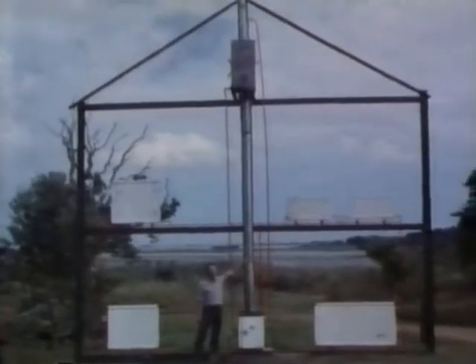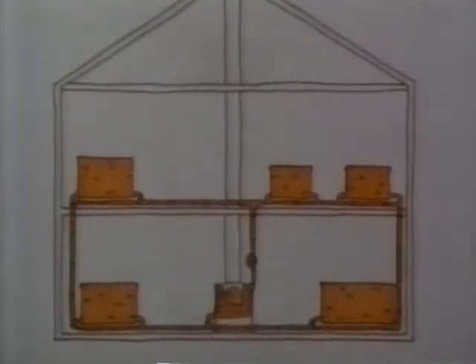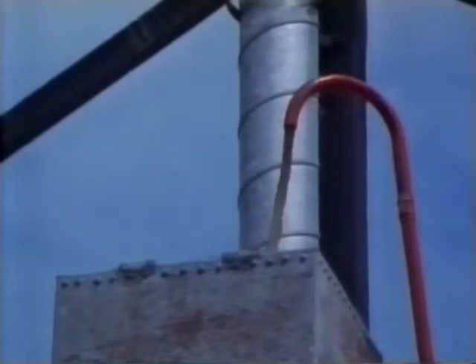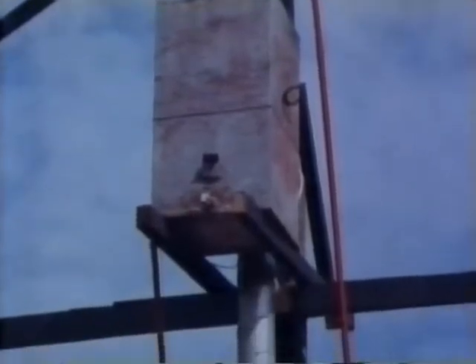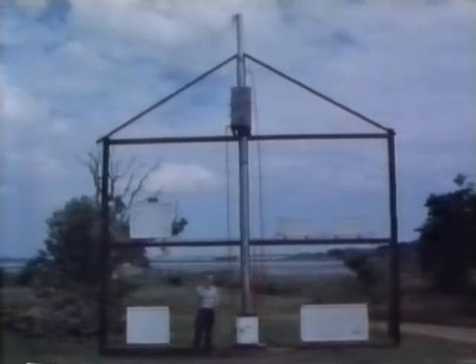It's basically very simple. Water is heated in a boiler by a fire and the exhaust gases go up the chimney. The hot water is pumped through a series of radiators and eventually returns to the boiler to be reheated again. The pipes around the boiler do look a bit complicated. There's one pipe to a tank in the roof to fill the system with water. There's also a vent pipe which lets the water inside expand as it heats up and lets water and steam out in case it boils. Here we've deliberately overheated this system and the steam harmlessly comes out of the vent while fresh water comes in through the feed pipe to stop the boiler boiling dry. Of course this doesn't normally happen — the boiler is actually rather inaccurately named as the water is never intended to boil. Most boilers also provide the hot water for the house, which creates even more pipes that we've left out on this model.